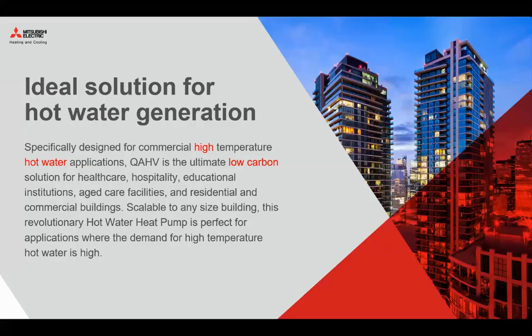So what is QAHV? Why do we feel it's important to introduce it to the Canadian market? Because we feel it is an ideal solution for hot water generation. It can create high temperature hot water, and because it's utilizing CO2 refrigerant, it is considered a low carbon solution. It can be used where you need a lot of hot water or high temperature hot water, for example, healthcare, hospitality sectors, education, schools, institutions, aged care facilities, long-term care homes, residential or commercial buildings. Whether it is winter or summer, we always need hot water throughout the year. So we feel it's a good fit for our market when the demand for high temperature hot water is high.